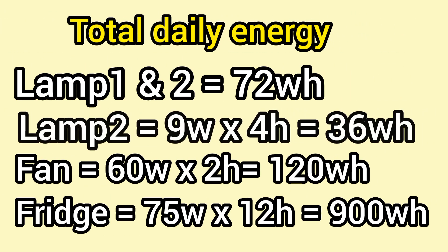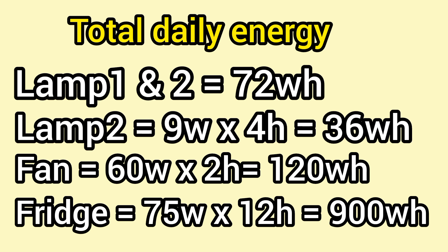Let's do the calculations. Lamp one: 9 watts multiplied by 4 hours gives us 36 watt-hours. Lamp two is also 9 watts used for four hours, giving another 36 watt-hours. The fan is rated 60 watts used for two hours, giving 120 watt-hours. The refrigerator is 75 watts used for 12 hours, giving a total of 900 watt-hours. The compressor doesn't run the full 24 hours because of the thermostat — it cuts and starts again.